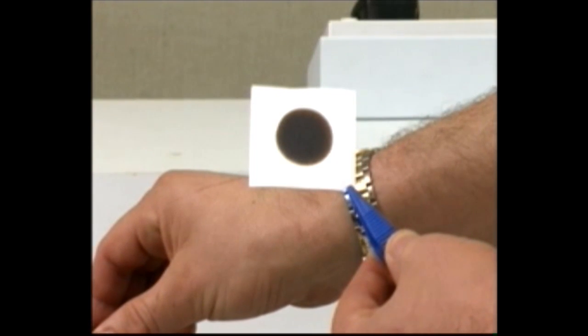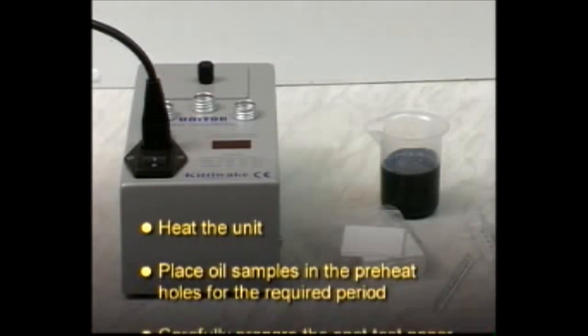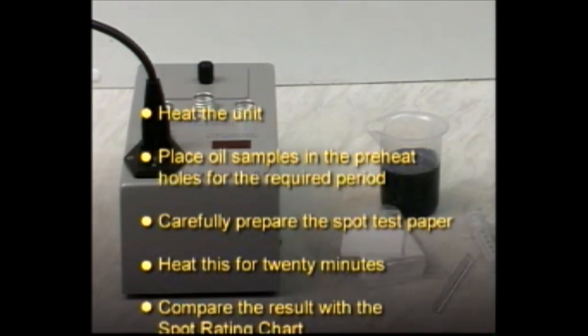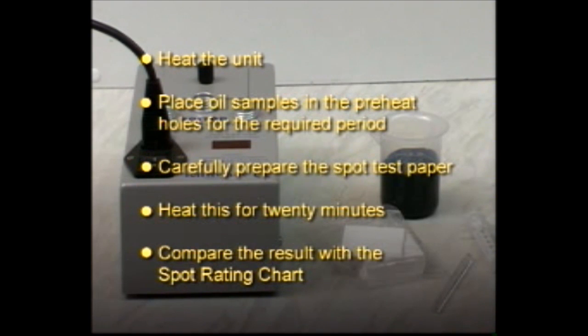To summarize, heat the unit. Place oil samples in the preheat holes for the required period. Carefully prepare the spot test paper. Heat this for 20 minutes. Compare the result with the spot rating chart.